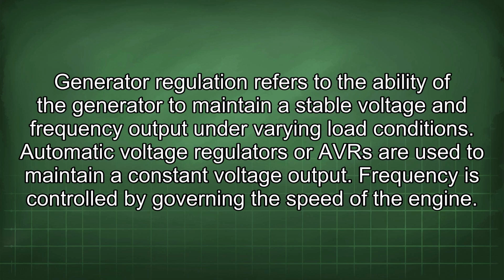Generator regulation refers to the ability of the generator to maintain a stable voltage and frequency output under varying load conditions. Automatic voltage regulators, or AVR, are used to maintain a constant voltage output. Frequency is controlled by governing the speed of the engine.